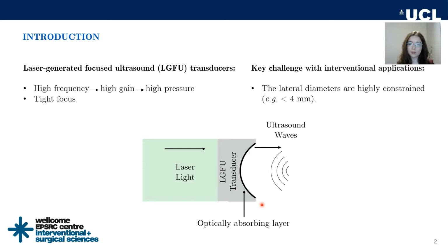Compared to conventional piezoelectric transducers, it is more feasible to generate high-frequency ultrasound with LGFU transducers, which leads to high gain and achieving high pressures at the focus with a tight spot. So the interest in LGFU transducers stems from these advantages.